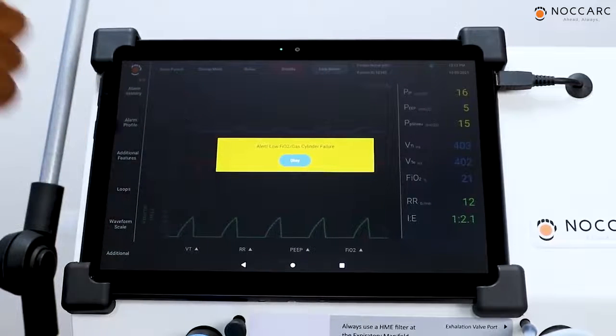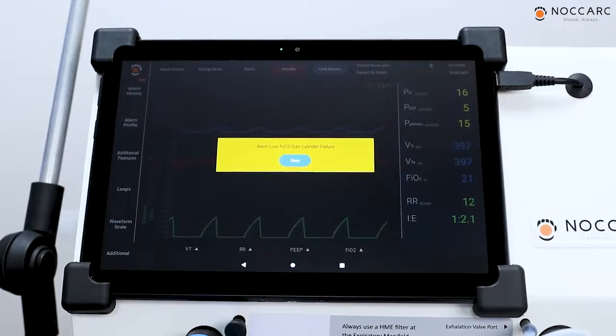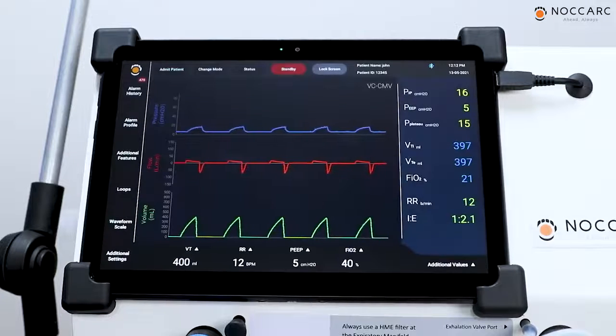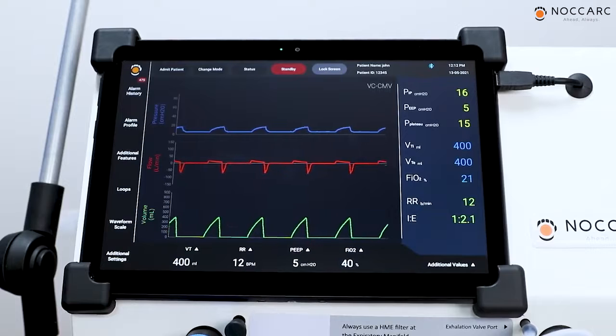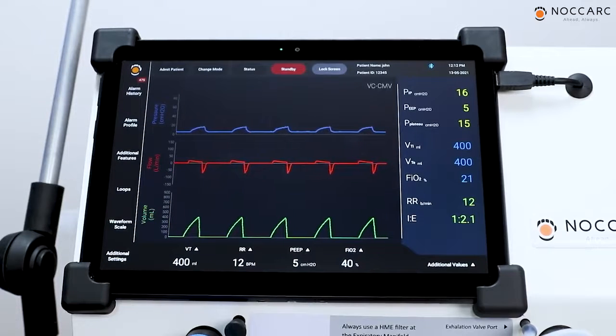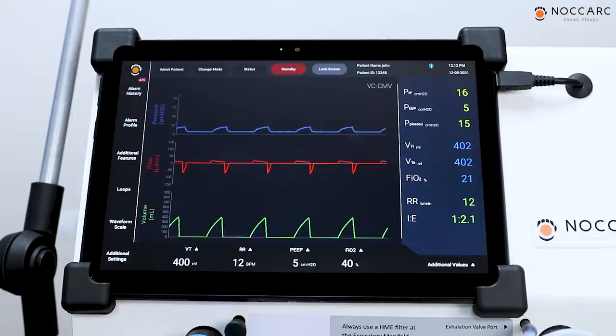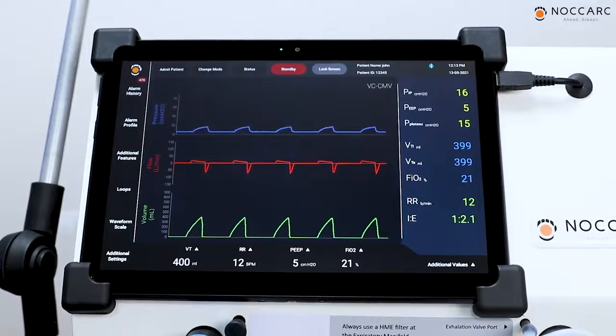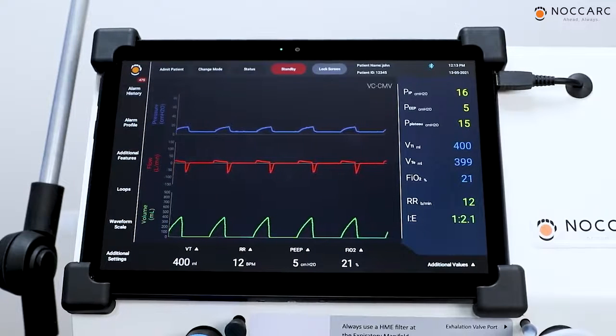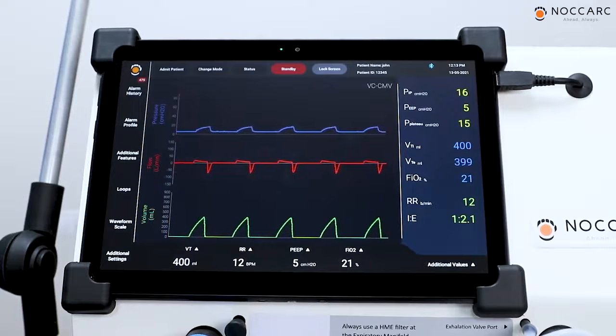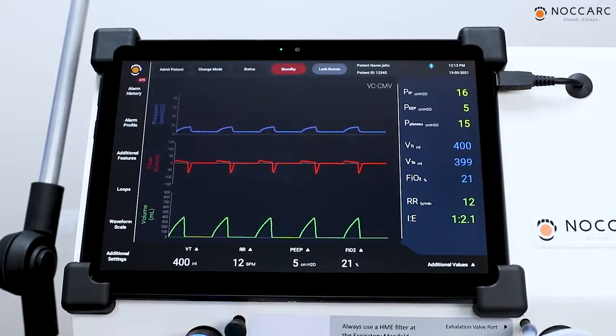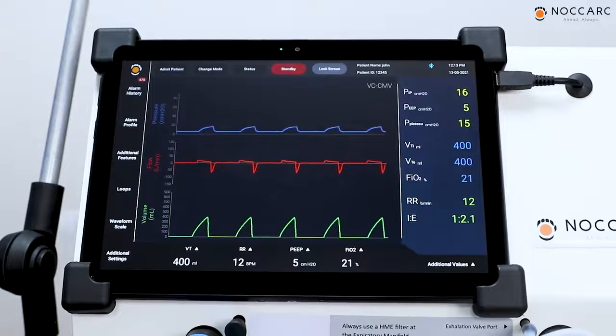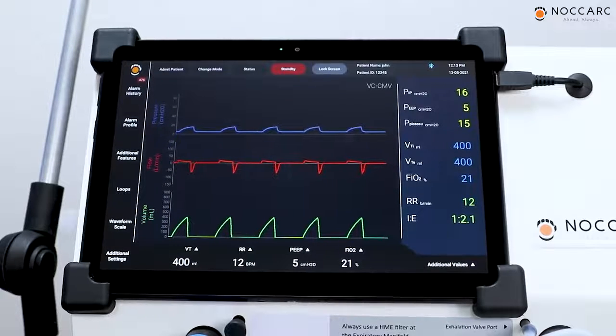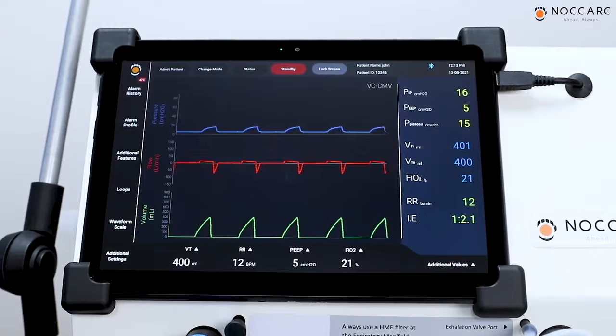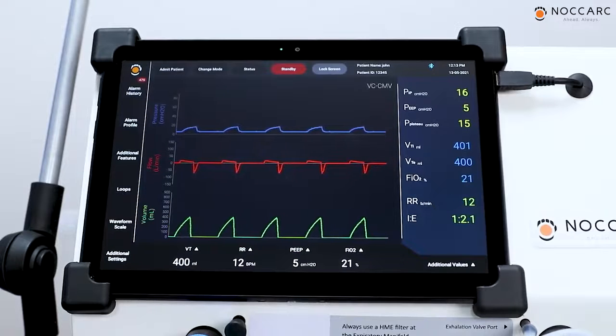Here you can see low FiO2 or gas cylinder failure alarm is coming on the screen. That indicates your FiO2 is not delivering to the patient, or oxygen line is failed, or oxygen sensor may be failed. In this condition, oxygen's mainline pressure may be low, or oxygen sensor is showing wrong readings. User has to ensure the main oxygen line pressure is proper, and user needs to perform pre-use check for proper working of oxygen sensor.